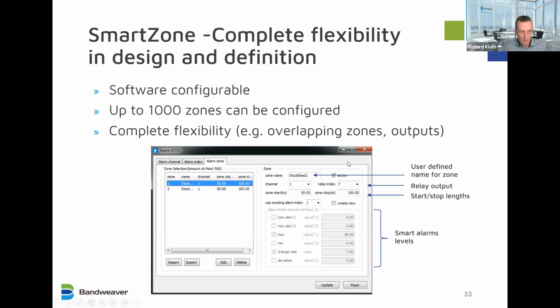And finally, on the smart alarms, smart zones: the zones themselves, you set these in the software and it gives you complete flexibility in design and definition of the zones. So this is an example of the user interface when you're defining them through the software. You can have up to 1,000 zones. You can have complete flexibility. The zones can be overlapping. You can have different outputs.